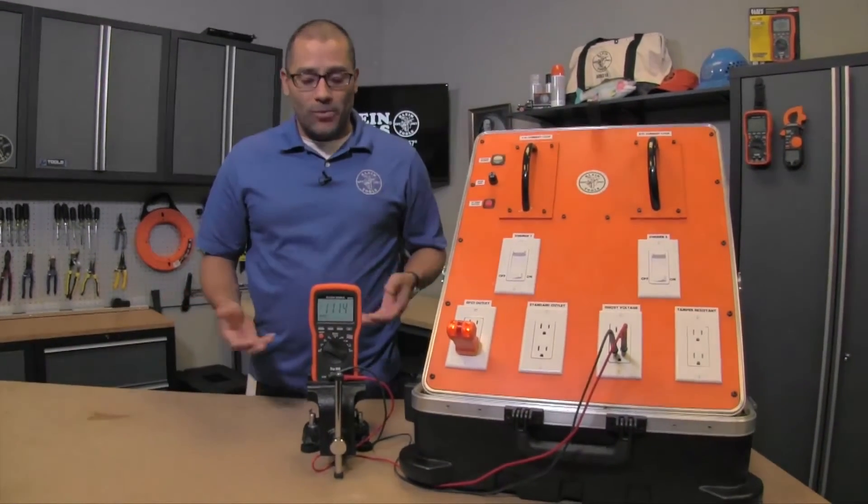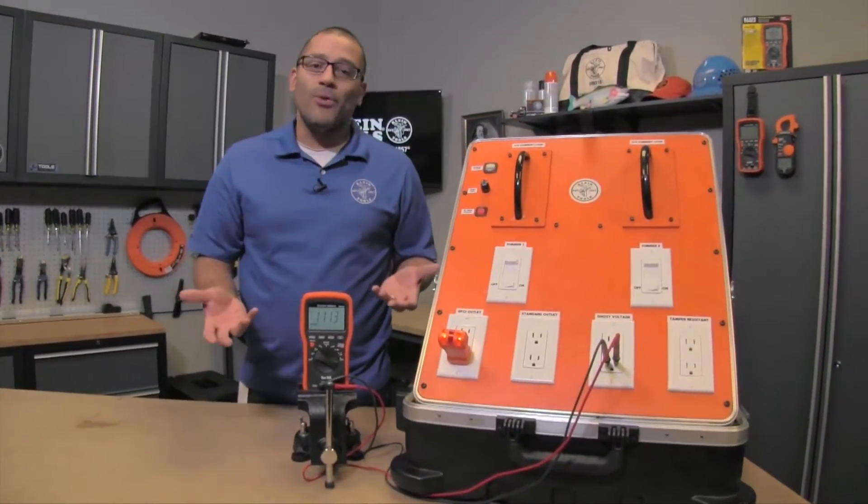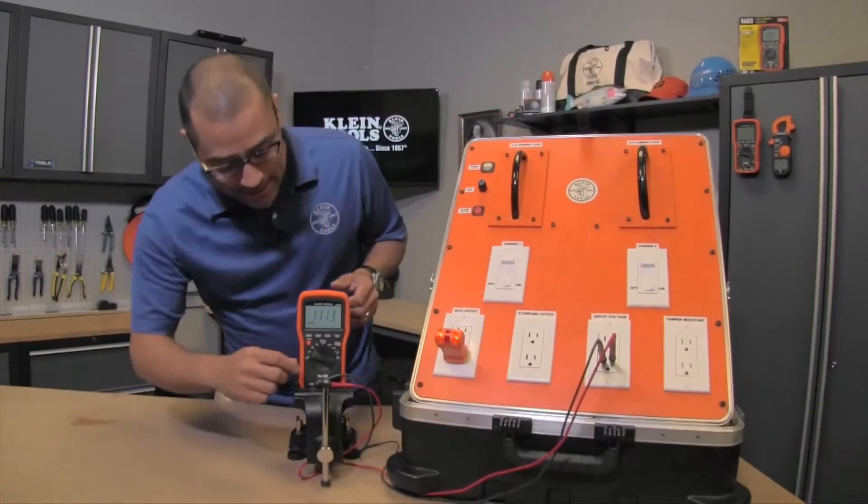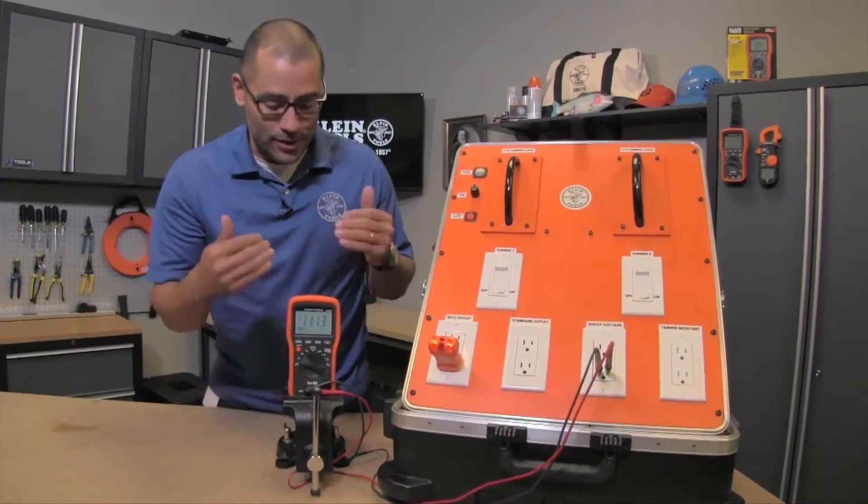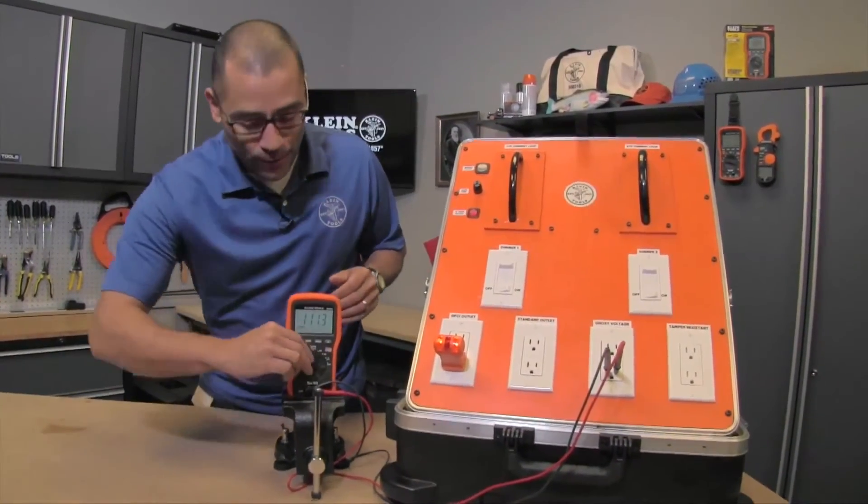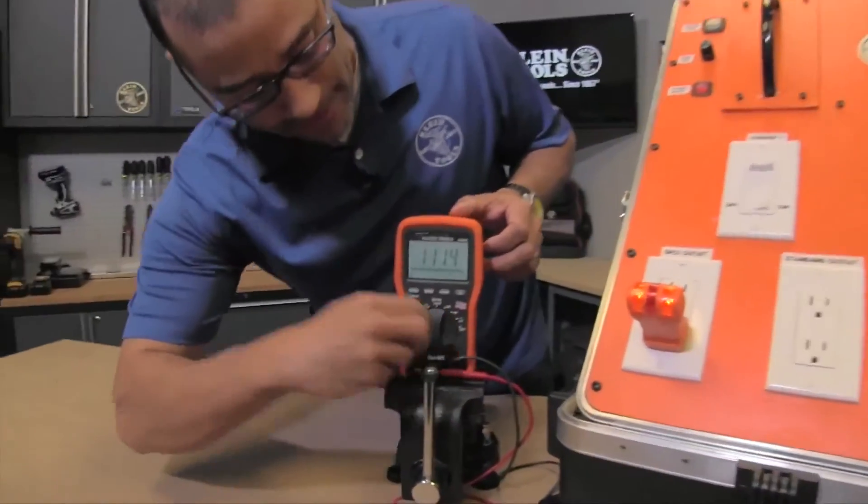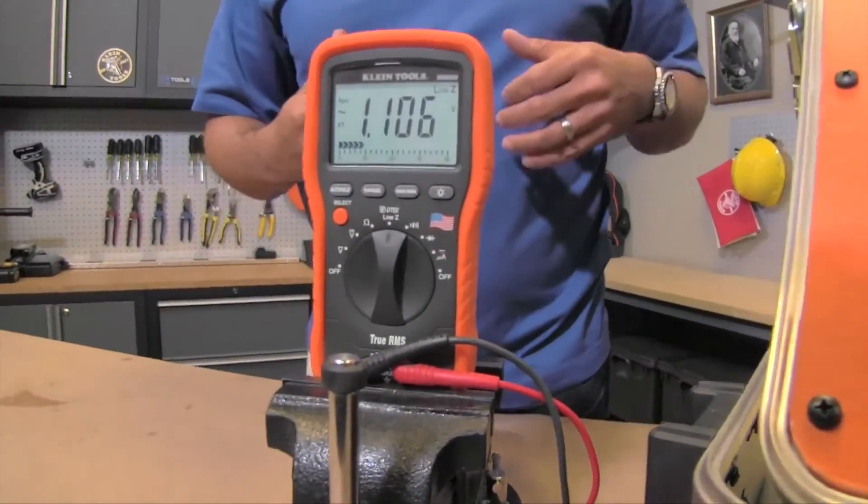So how would you troubleshoot that? Well low impedance is kind of your way to do that. What it does is it actually simulates a load. There's a thermistor inside the meter. When you flip to this feature you are actually drawing power now.